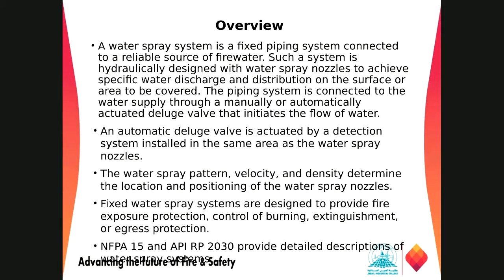Normally, the water spray system is fixed piping. We normally call it the deluge spray system, right? In a deluge spray system, we have open nozzles, which are intended to protect flammable liquid stored inside a vessel, heat exchangers, or storage tanks, and we protect that for cooling purposes, to cool the exposed surface. If there is a fire in a nearby area, we need to control the other equipment present in those areas, just to control the temperature, so that the temperature of the steel is not going higher.